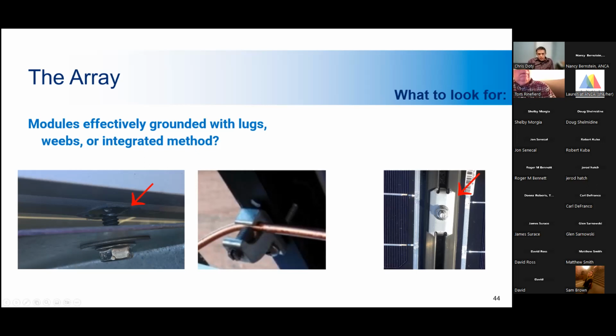But like I said, it's critical that the equipment that's used to bond and ground the system is suitable for the environment and the application. If the grounding method you use is not rated for the environment, it can fail, leaving the system energized and dangerous. Basically, that's a common theme throughout this whole presentation. If you are designing a system that's supposed to last 25 years plus, which these are, you need to design all of the components to last that long. You don't want to install it and have some of the components last 10 years, and then you have hazards in the system.